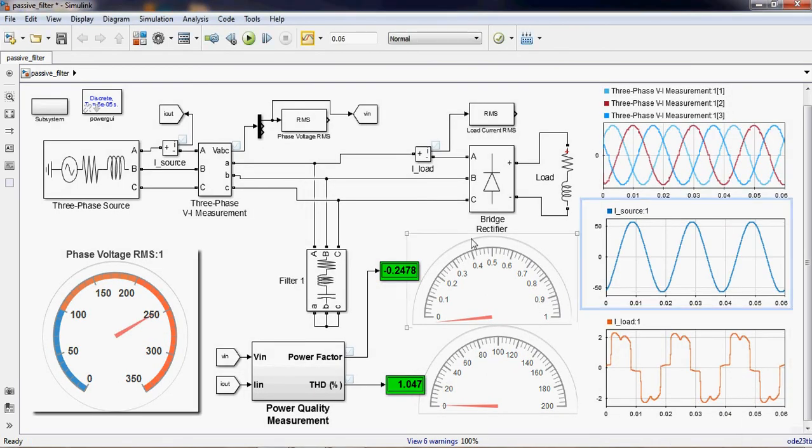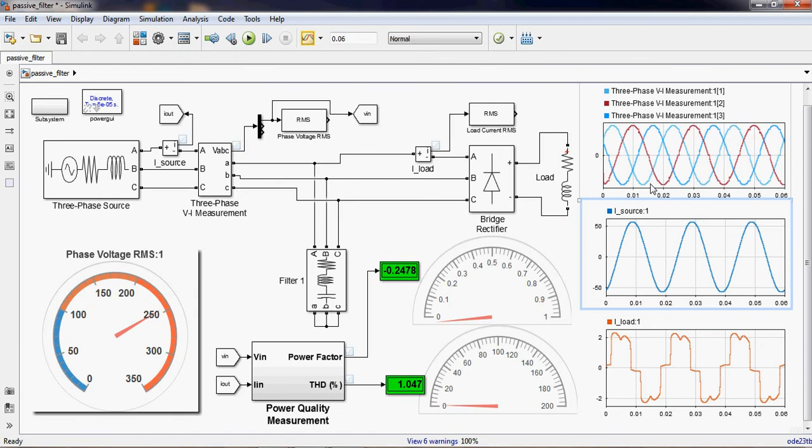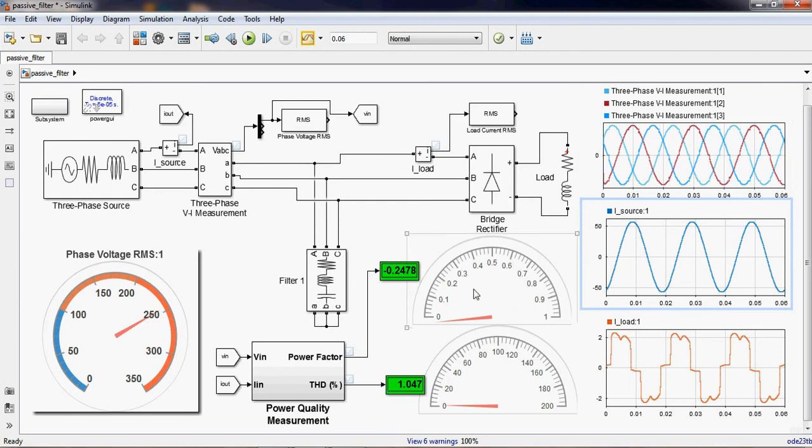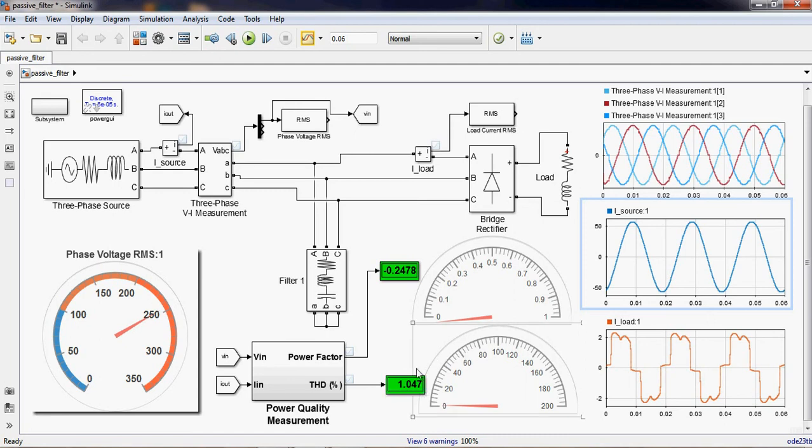Okay, now the signals are available. You can see in right hand side here, the three phase voltage has improved. Line current is nearly to the sinusoid sine current and the load is distorted. Distorted line current will not move towards the supply grid, that was our motive.